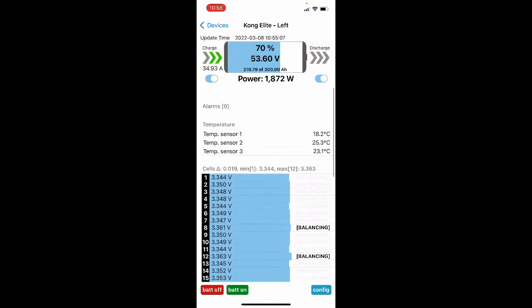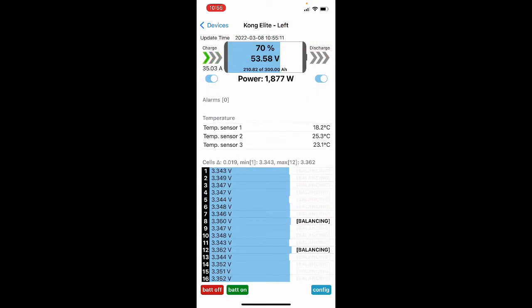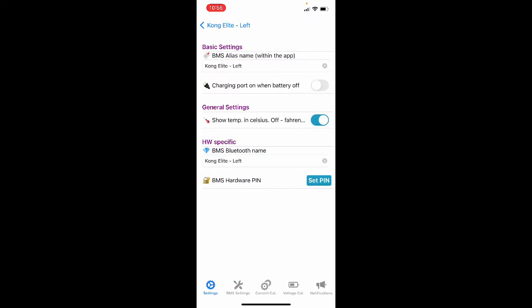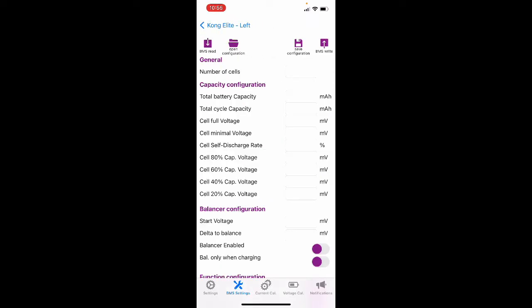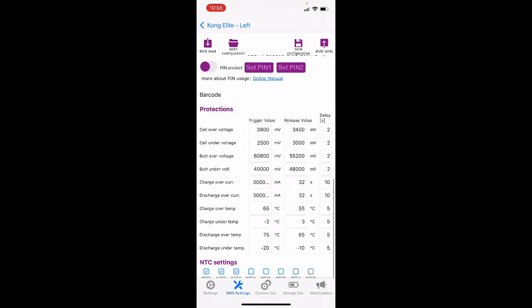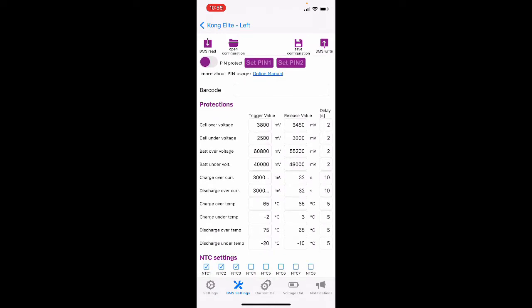Let me show you at what voltage it cuts the charge off. If you go to config, BMS settings, then BMS read, it shows you the protections. Cell over voltage is at 3.8 volts. When a cell hits 3.8 volts, it shuts off the charging. The BMS shuts off charging to itself, and that's what's occurring when you see those 12 incidents of shutdowns from over voltage - it's that 3.8 volt setting.